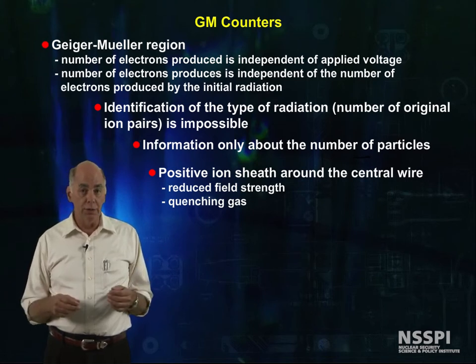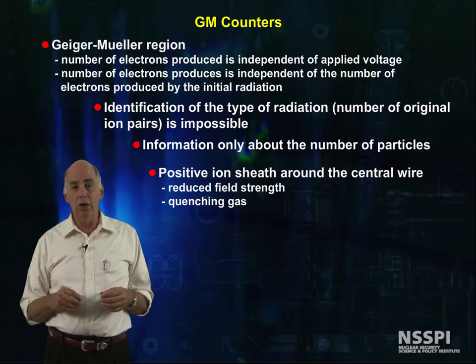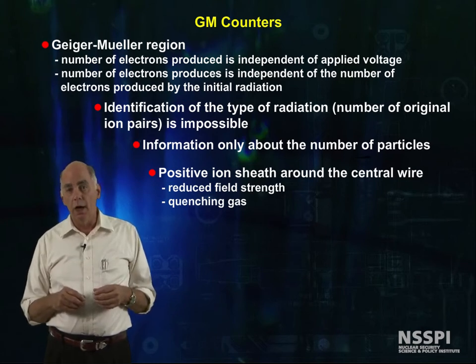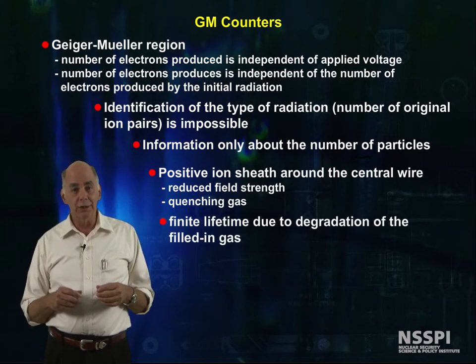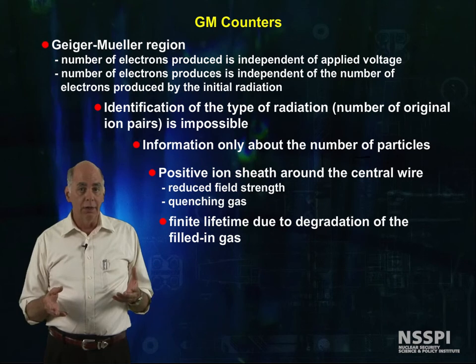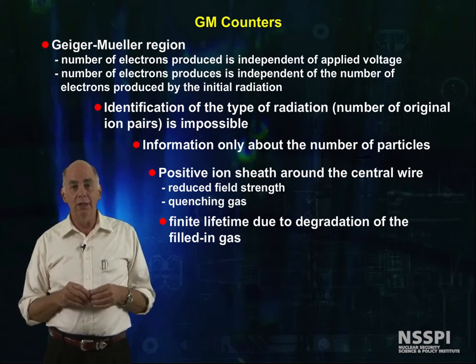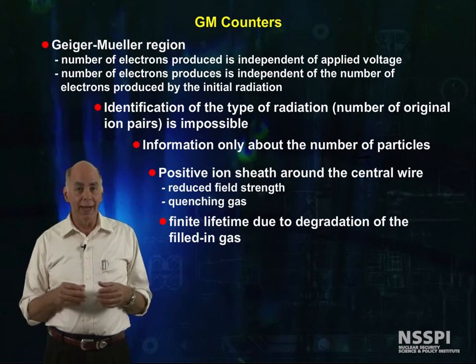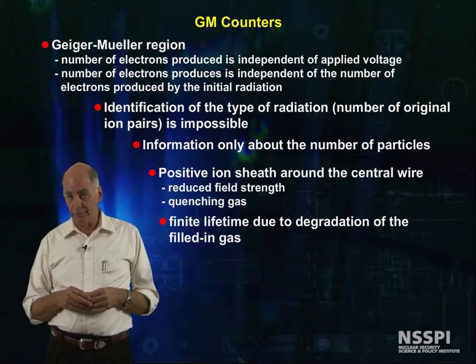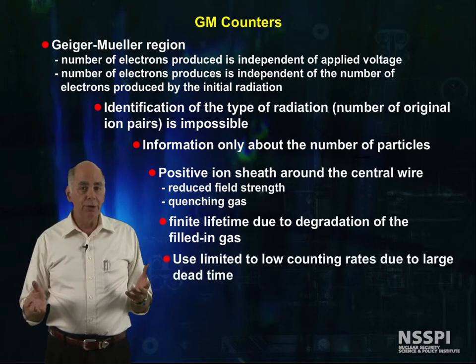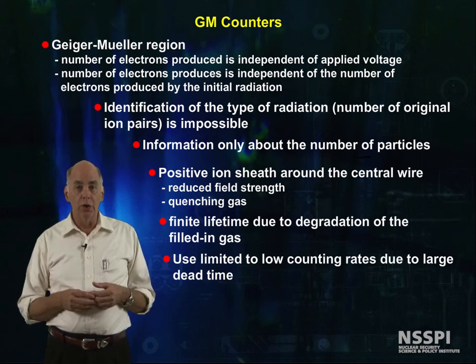Halogens can be used as quench gases, and they have the advantage of recombining later in the tube. Other quench gases can be used, but if they don't reform after use, then they limit the tube lifetime due to degradation of the fill gas. GM counters are limited to low count rates due to the large dead time for each count.